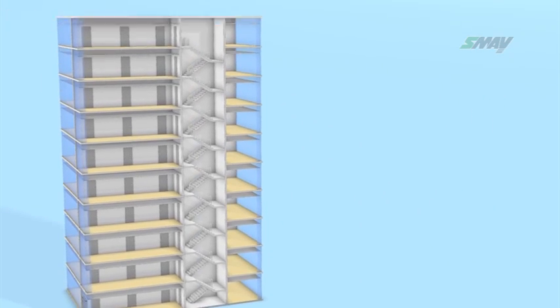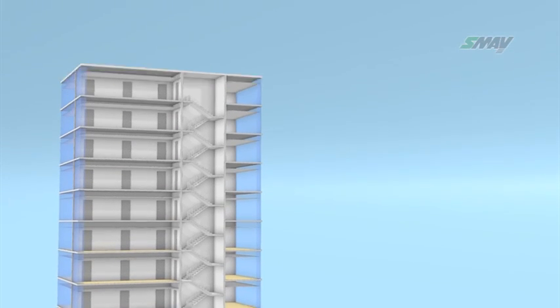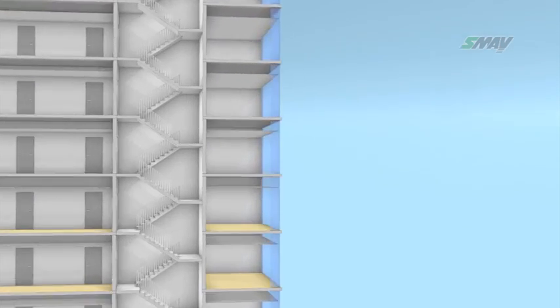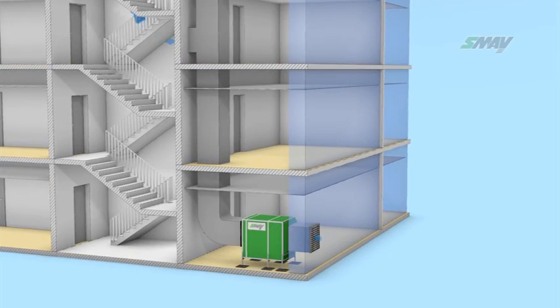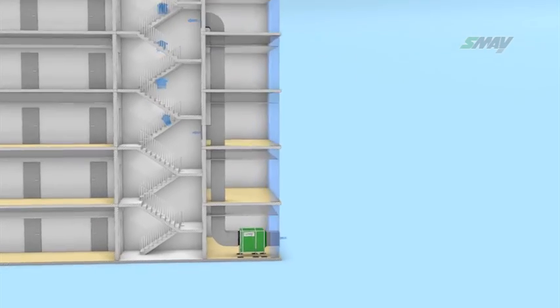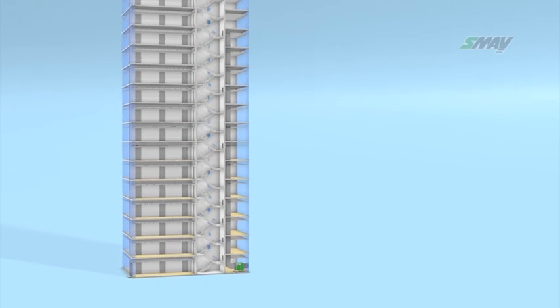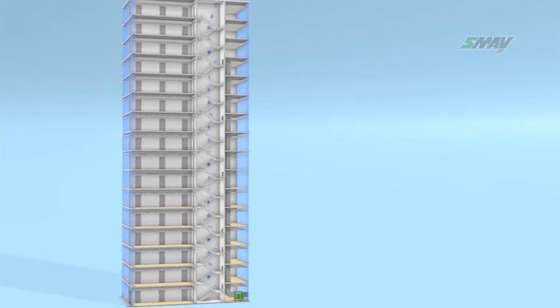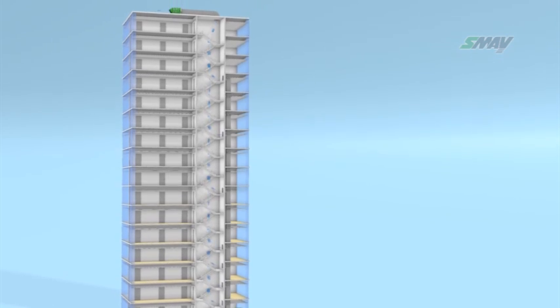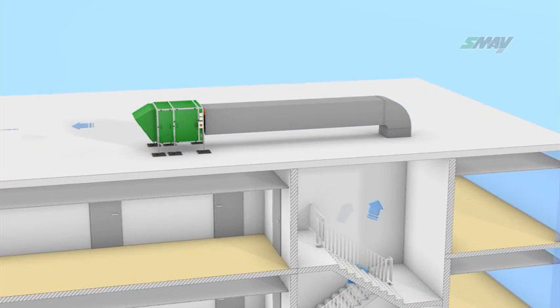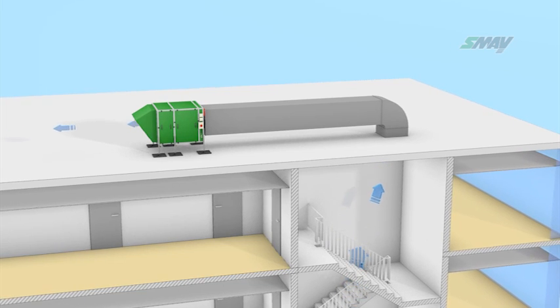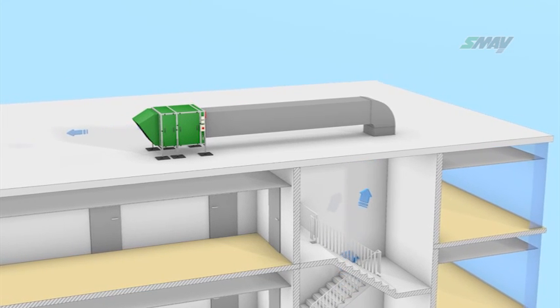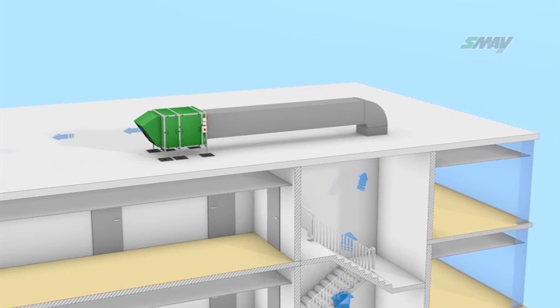In case of higher buildings, it is necessary to use two unidirectional iSWAY FC units. The task of the first device supplying air to the staircase is to produce and control overpressure in the staircase at the required level and generate directed airflow inside the staircase. The task of the second upper unit is to prevent the increase of overpressure in the upper part of the staircase, which may result from the stack effect.